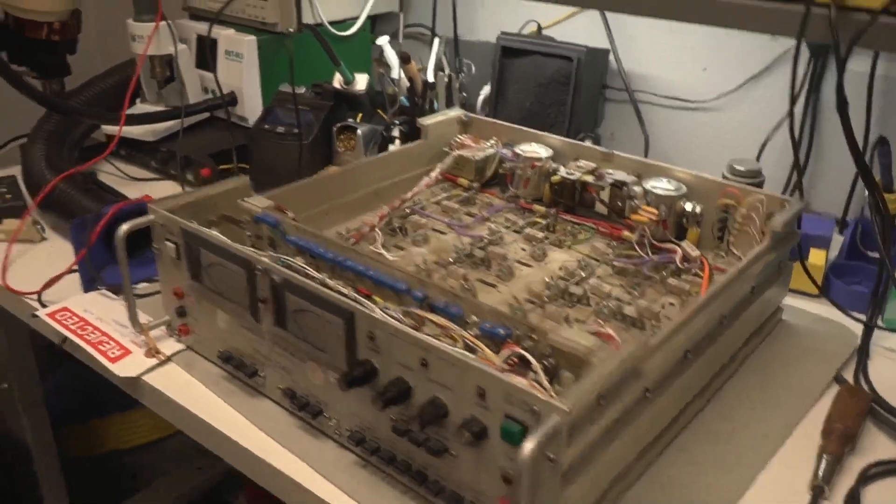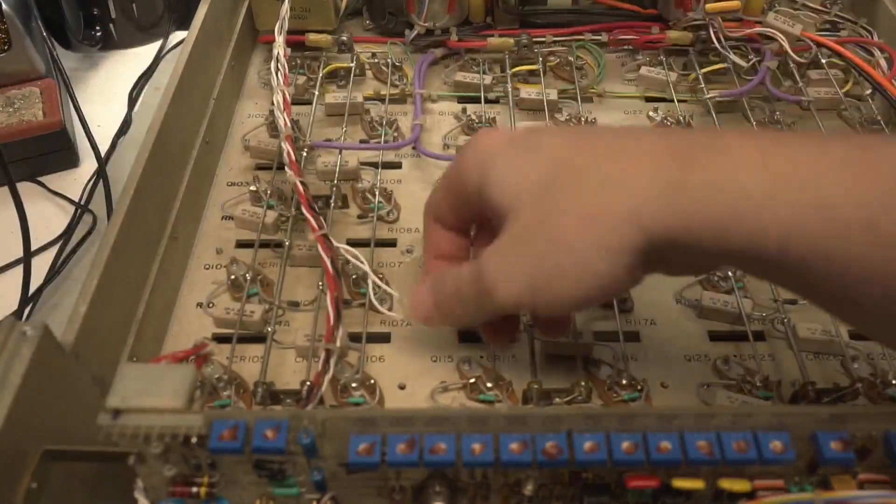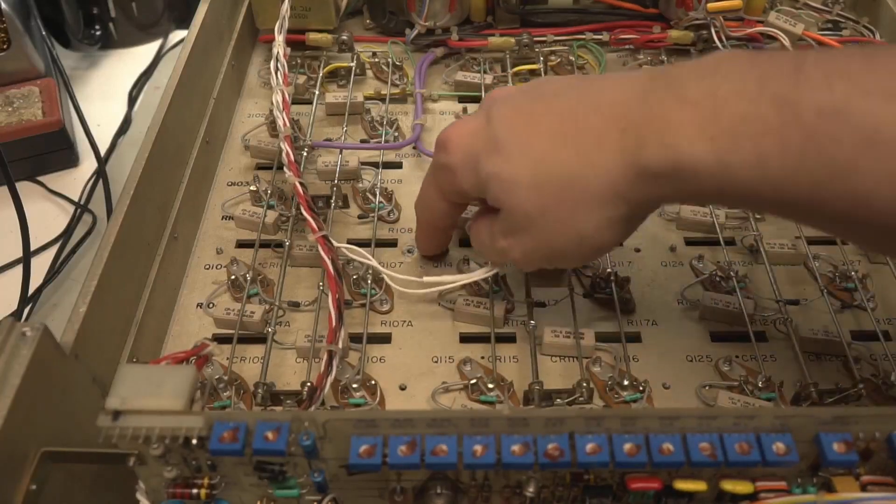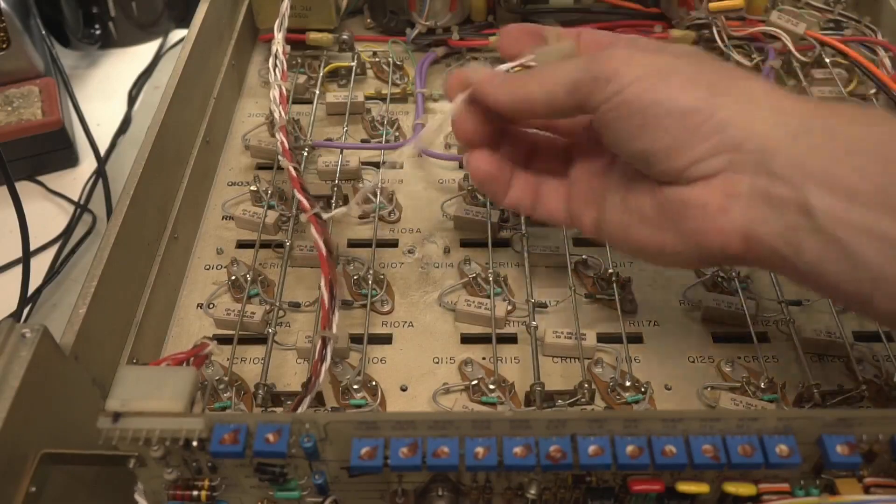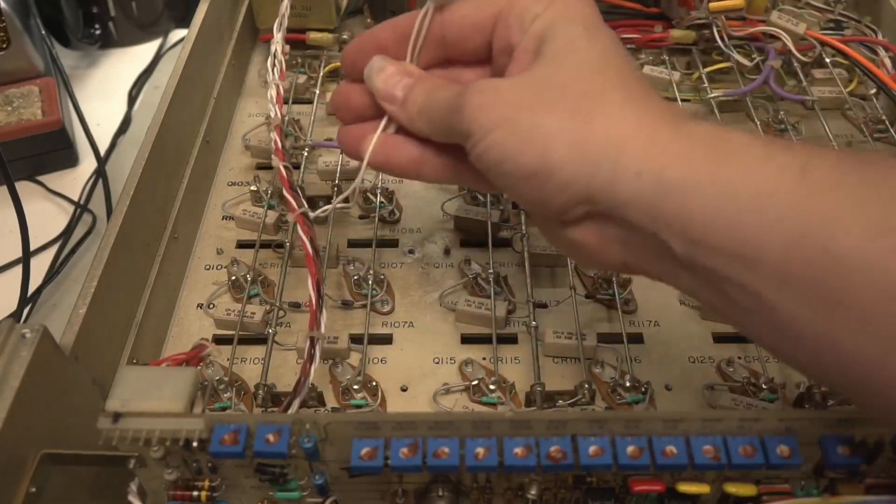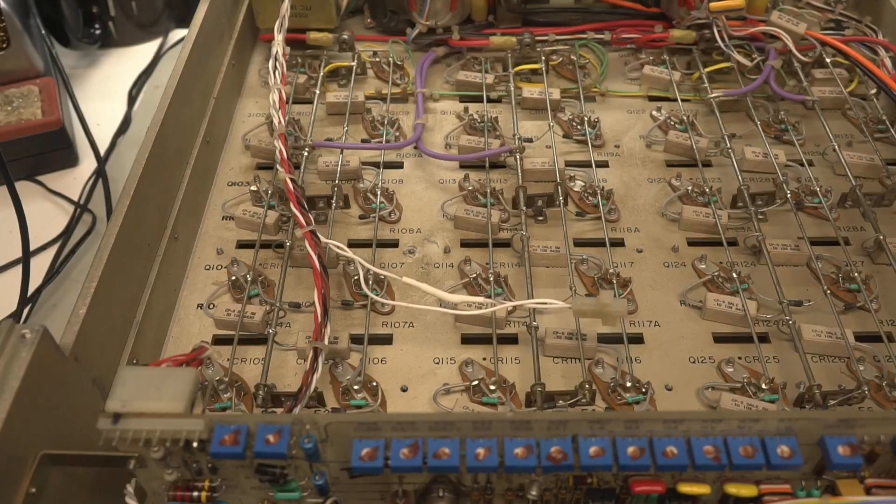First thing I'm noticing, let me bring the camera around. All right, the first thing I'm noticing is it looks like the thermal switch had broken off of here and they just kind of patched it like that, so the fans are going to run all the time on this thing.